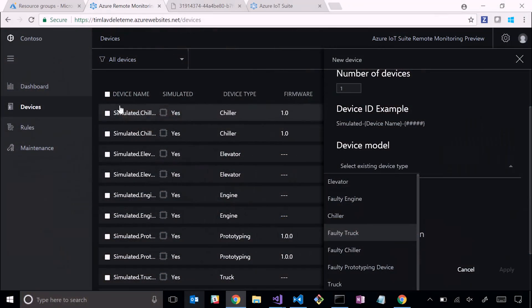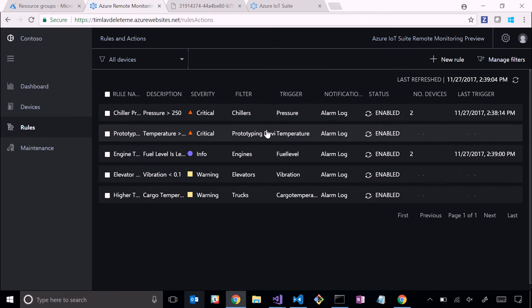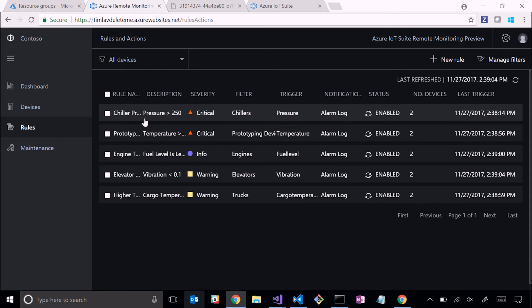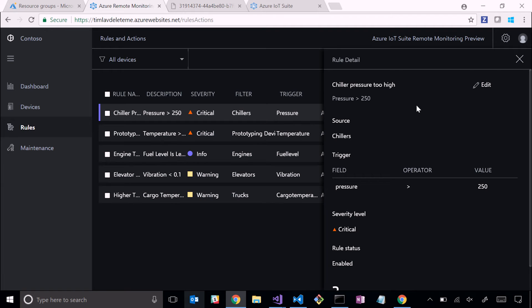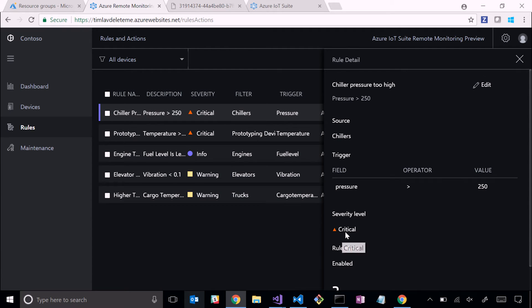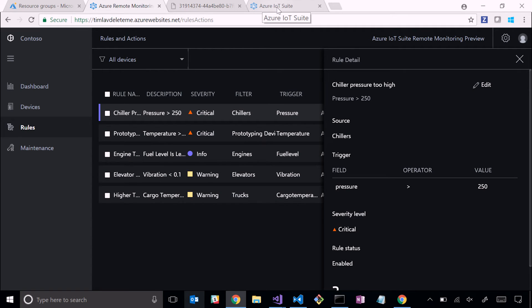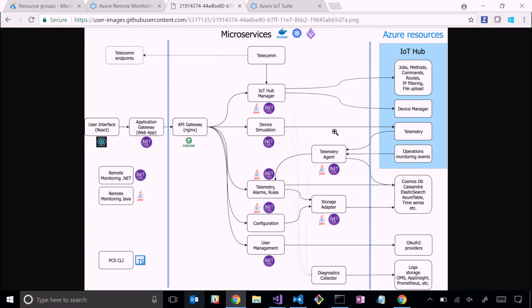It does allow you to create these devices, have a flow of simulated data or real data coming in and display it. But you also have rules - you can adapt the rules. In box we ship with a number of rules that run against the telemetry stream coming from our simulated devices. This particular rule is a rule for a chiller. This chiller is saying if pressure is greater than 250, then I want you to generate a critical alarm, and this particular rule is enabled. I could edit the rule or create my own new ones. Right now it's our code - we have this telemetry agent which is doing processing over that stream of telemetry data, then using that rule to evaluate that telemetry stream to generate an alarm.